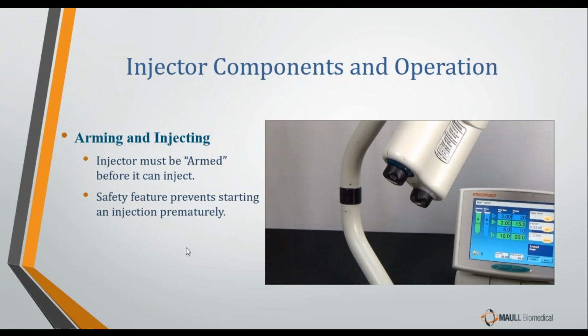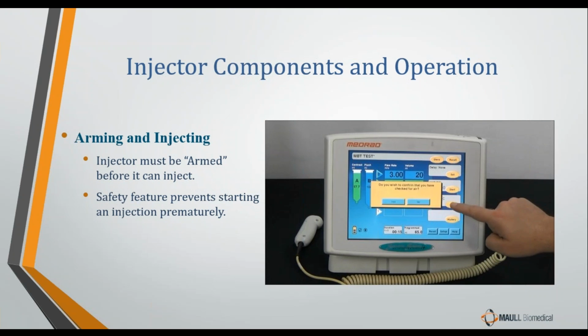Now, arming and injecting, actually performing an injection. Before we hit the start switch and it actually starts making fluid come out of the end of it, we have to arm the injector. As soon as we arm the injector, there's some visual indicator to the operator that the injector is armed, and if they hit that button, it's going to start injecting.